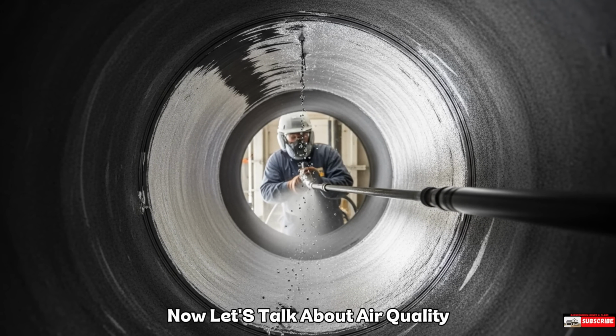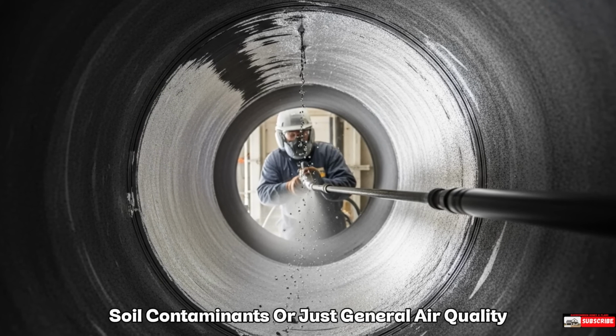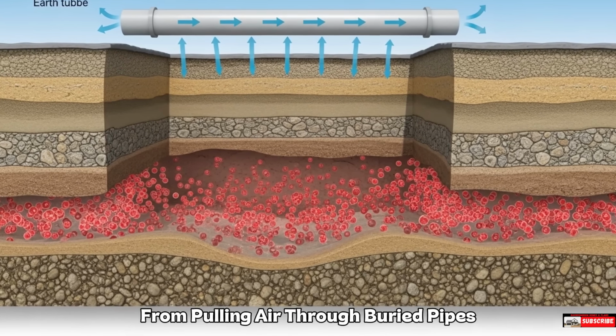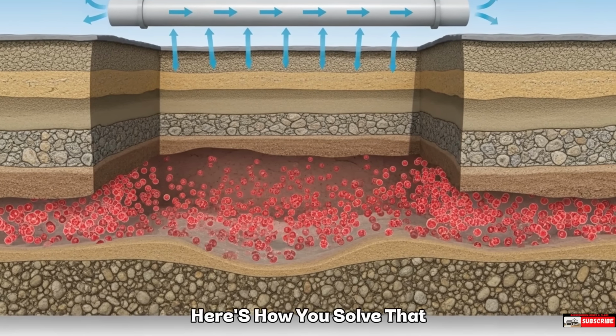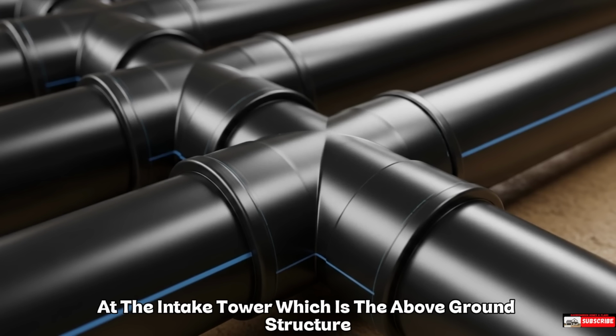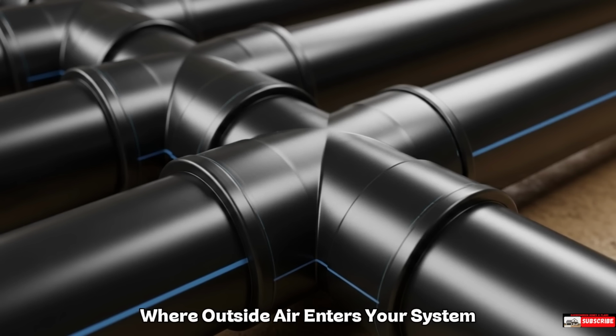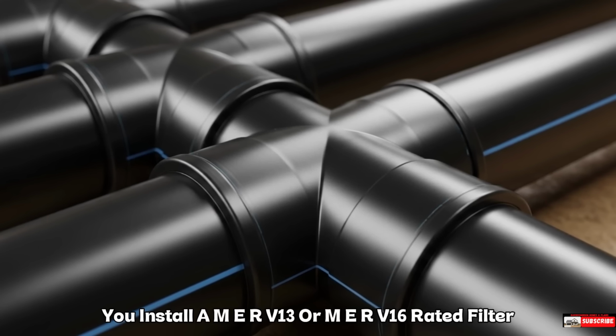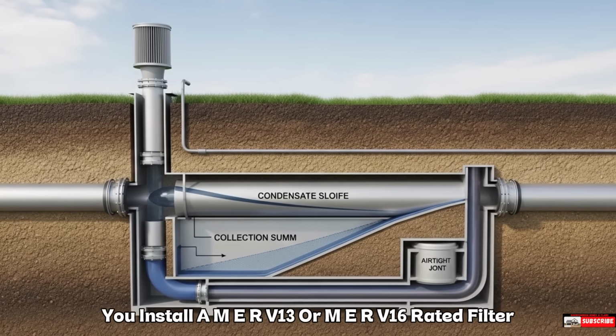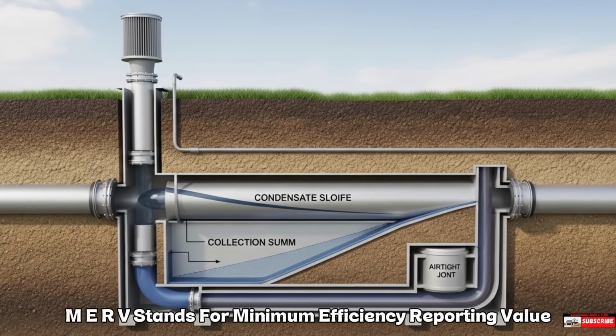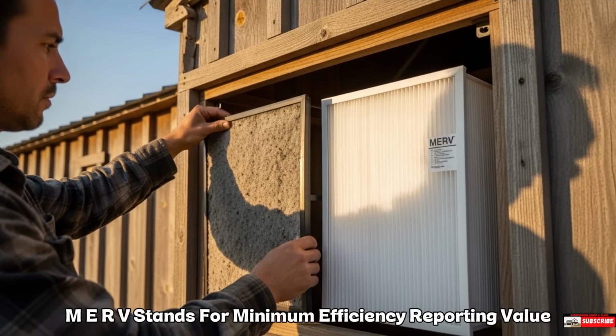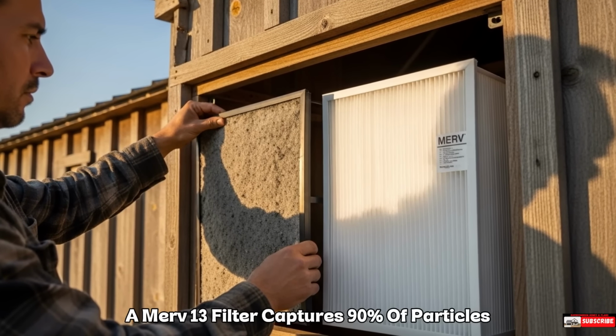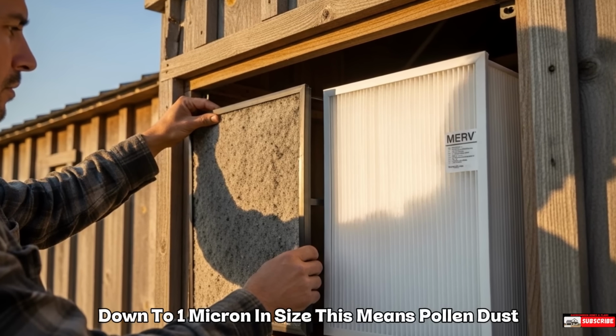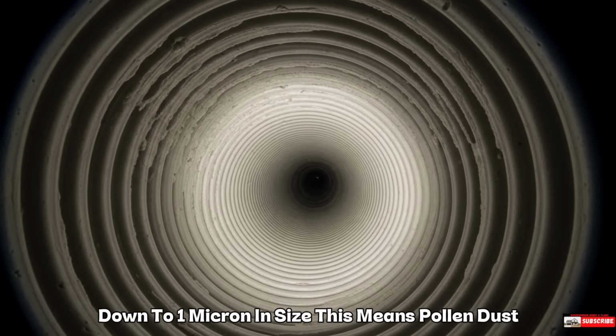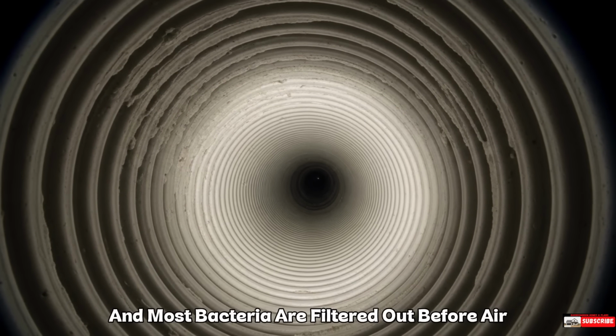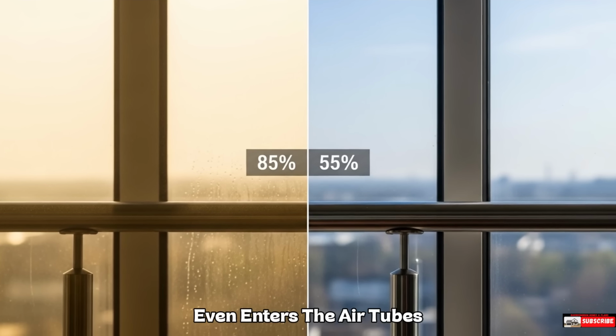Now let's talk about air quality. Some people worry about radon gas, soil contaminants, or just general air quality from pulling air through buried pipes. Here's how you solve that. At the intake tower, which is the above-ground structure where outside air enters your system, you install a MERV13 or MERV16 rated filter. MERV stands for Minimum Efficiency Reporting Value. A MERV13 filter captures 90% of particles down to 1 micron in size. This means pollen, dust, mold spores, and most bacteria are filtered out before air even enters the earth tubes.